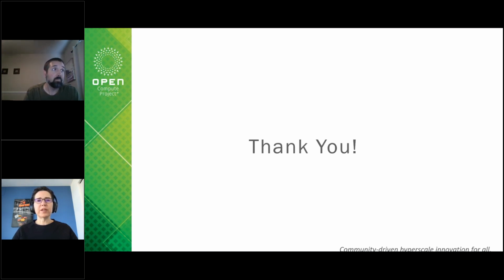Thanks, Jeff. And the second question is, is there a specific reason that you're using a JBOD for the system? So what we do for our JBOD portion is we use that in something called cold storage, where it's optimized for low power. So what we try to do is remove everything we can and turn off as much stuff as we can. We're not too worried about how slow it is to retrieve the data. I mean, we are, but it's less sensitive, right? So the goal there is to eliminate as much power. The CPUs generate quite a bit of heat, so that was kind of the motivation behind that configuration.